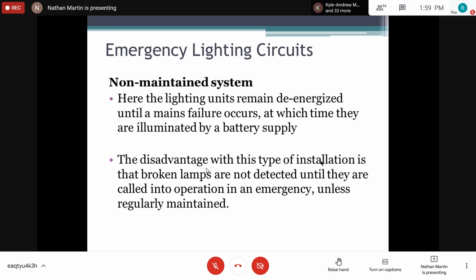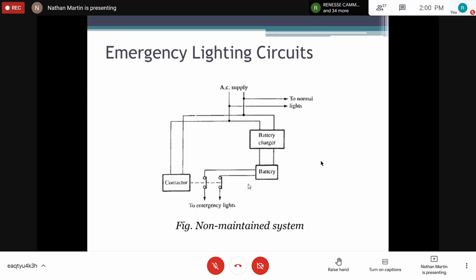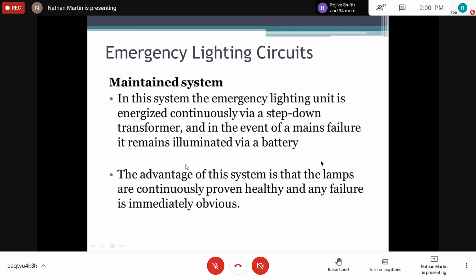The non-maintained light: here the lighting units remain de-energized until mains failure occurs, at which time they are illuminated by a battery supply, right? The disadvantage with this type of installation is that broken lamps are not detected until they are called into operation. So you have to service them regularly, either with your Monday checks or your monthly checks and so forth. But a lot of times when they install these lights, it's only when the power goes that you know they are not working. And that's really the main disadvantage of this type of system.